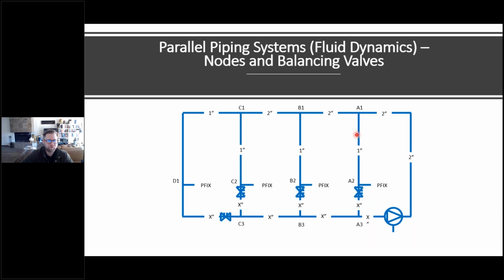In order to get the flow to not just flow into the A loop, we put on these balancing valves. If we didn't have the balancing valves in there, such as that I showed before, all the water would take the path of least resistance, which would be in this A loop. You would not see any circulation or recirculation of flow going out to this B, C, or D loops. But by putting in balancing valves in the A loop, the B loop, C loop, and D loop, as we discussed during our last meeting, this balancing valve will be the one that's likely the most closed, followed by this one, and the D loop would likely be the most open.